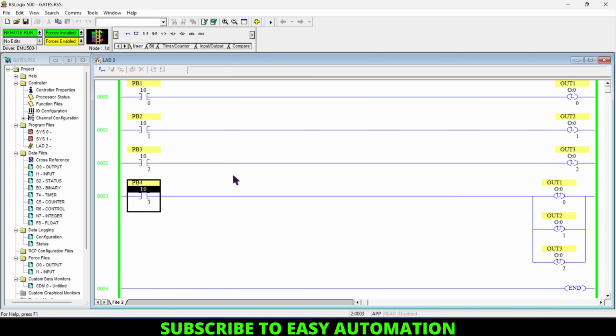Now our program is in idle condition. It means no output is on and no push button is pressed. So now let's press our first push button. I have pressed this first push button and released it. Then our first output will turn on here, and if I press our second push button and release that one, then our second output will turn on here. If I press our third push button, then our third output will go on, and I release it, and the output is still on.